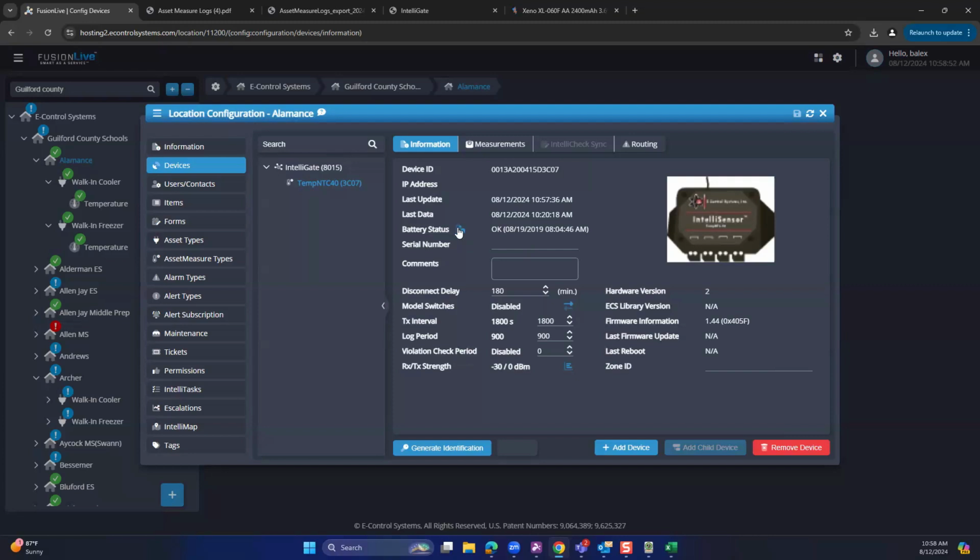If we get some low batteries, you're going to get a critical battery alarm. We generally see the batteries, once you start getting that alarm, last anywhere from 2 to 5 days on average. So we'll just let you know, once you start getting those critical battery alarms, you have on average a work week to get those changed before the unit will die. If it dies completely due to the batteries, what we have to do is just change those batteries.